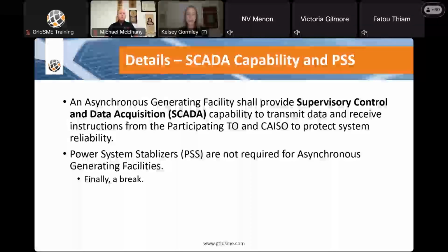No power system stabilizer devices are required because the inverter and plant controller can inherently provide fast voltage control. Dedicated power system stabilizer hardware is not required for inverter-based facilities. Traditional power system stabilizer devices are generally associated with synchronous machines. In inverter-based resources, the function is essentially replaced by the inverter's controls and fast reacting power electronics. So CAISO does not mandate a power system stabilizer on asynchronous generation as long as the plant overall can meet the dynamic performance criteria in other ways.